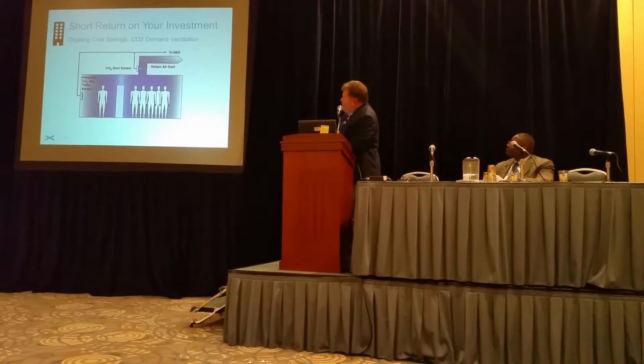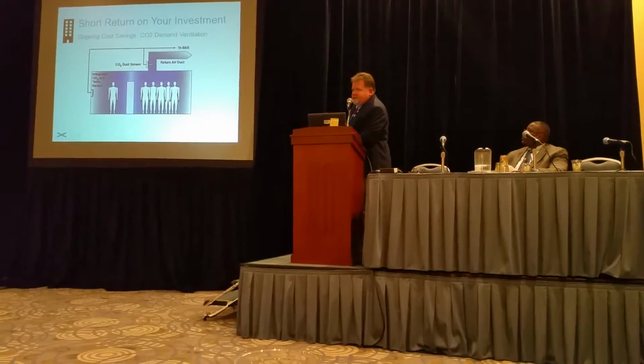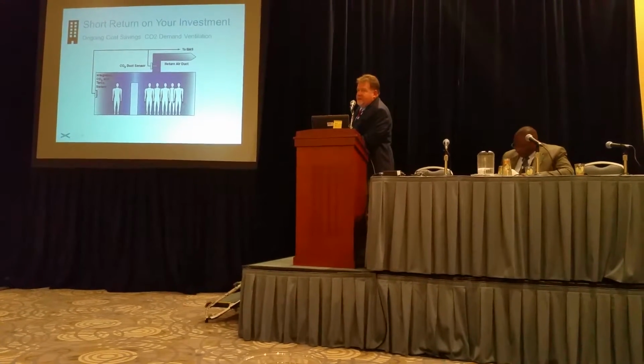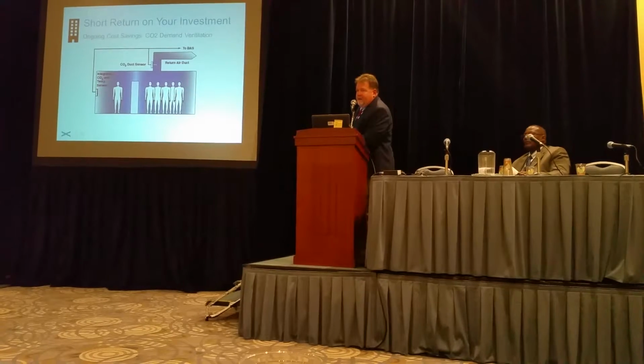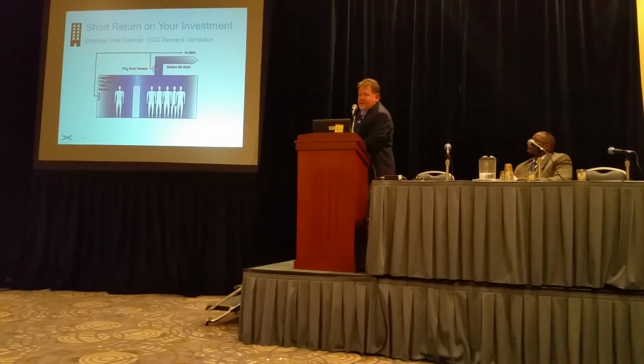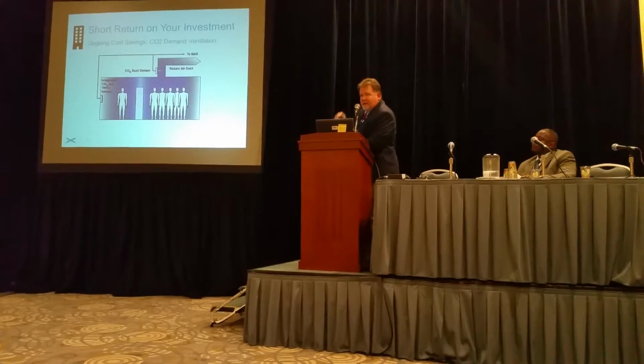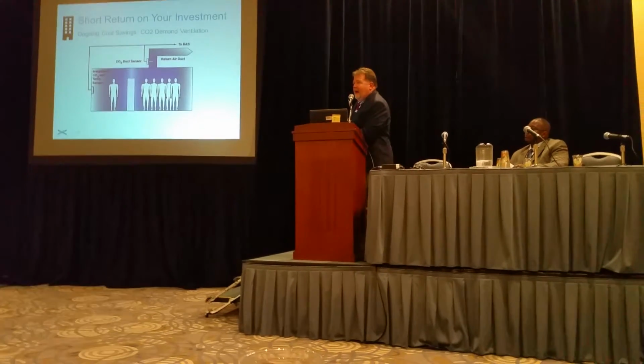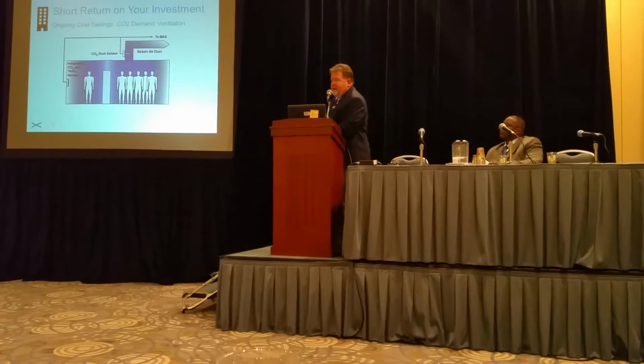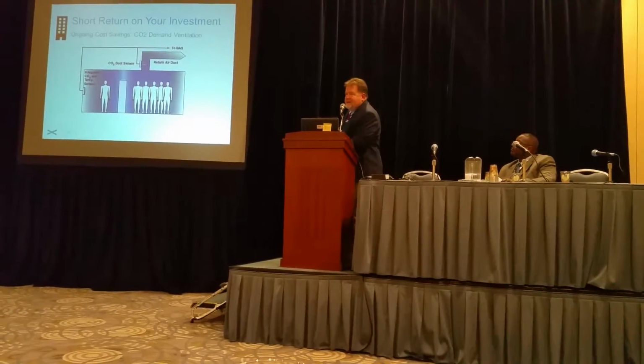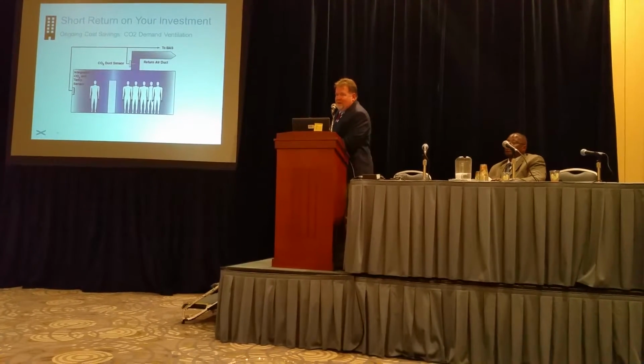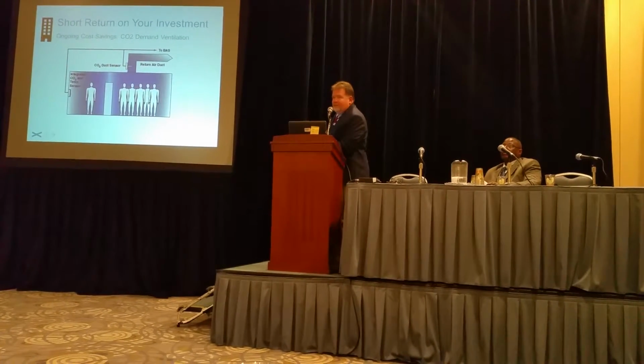Short return on investment, a lot of different strategies and different things you can do. Right now, this building may be set to hold 100 people. We have X amount of CFM of fresh air that has to come into this space right here because we're all breathing. We put sensors in here, and all of a sudden, it makes it really nice because if we only have 4 people breathing in here, then we're only bringing enough air for 4 people.